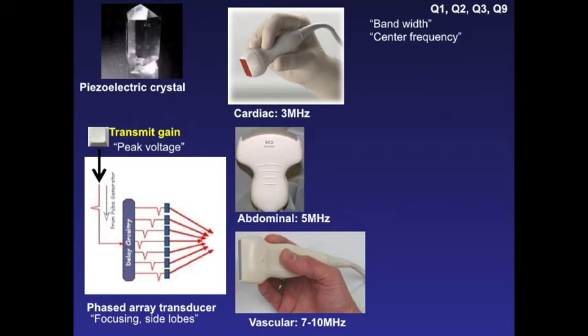Bandwidth and center frequency are reported for CLUE. It is between 4-2, which is 4 megahertz, to 2 megahertz as a bandwidth with a center frequency of 3 megahertz. So you'll see these ultrasound transducers labeled as 4-2 or 7-3, and these are all the representation of the bandwidth, with the higher frequency by convention listed first.